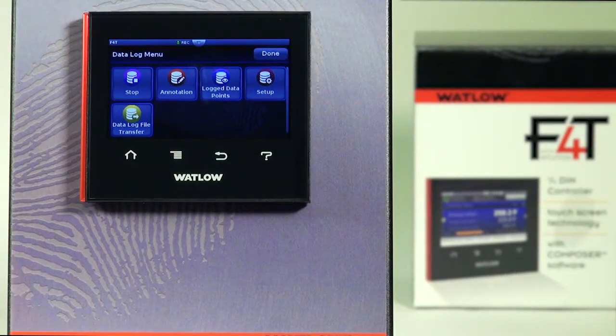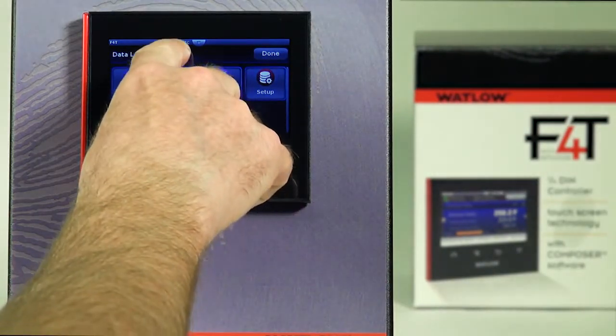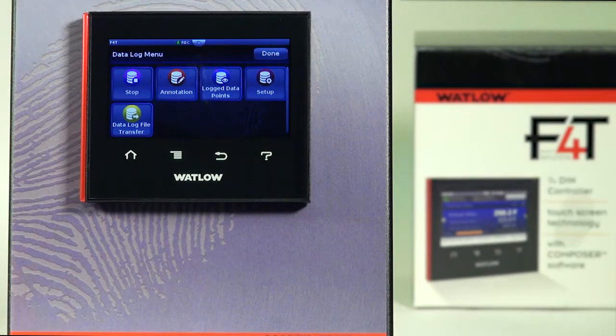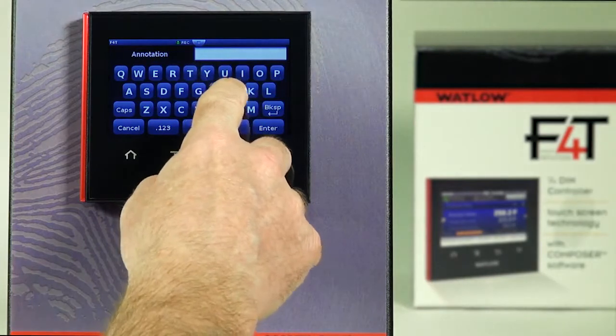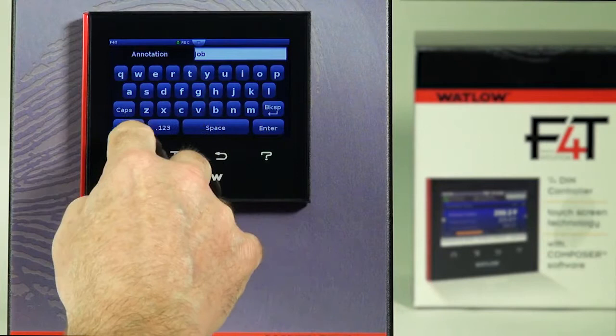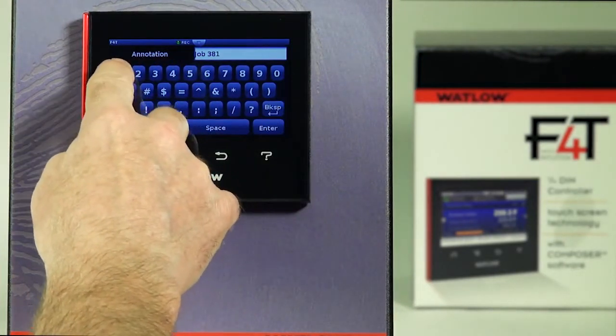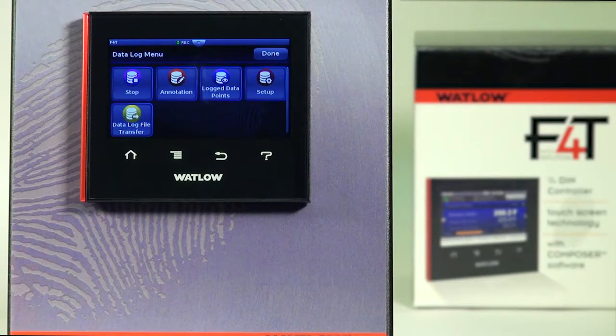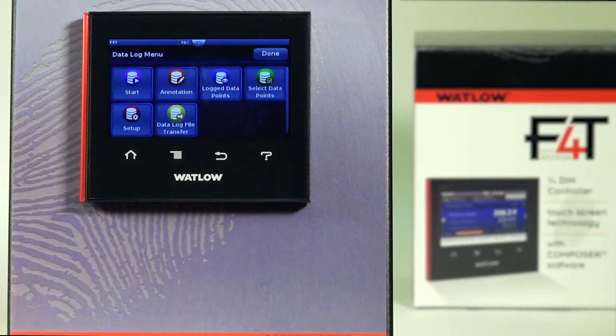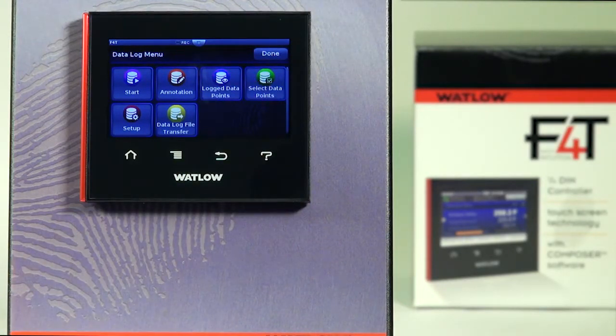You can also get confirmation without going into the setup page — there's a record icon at the top with a green indication that we're data logging. If you want to type in an annotation note, you can press here — for instance, to enter a job number or a customer number. When you hit enter, it will be date and time stamped into the data logging record. You could also type in the note before you start data logging, and when you hit start, that annotation note will go in the very first logged interval. Note that when you hit start and stop, the 'Select Data Points' icon disappears — while data logging you cannot actively turn data log parameters on and off.